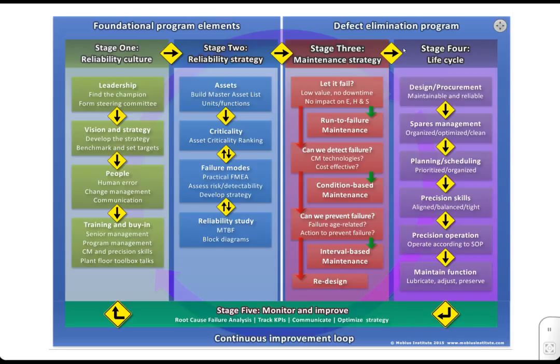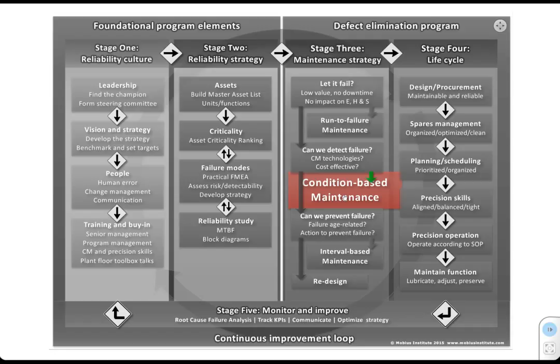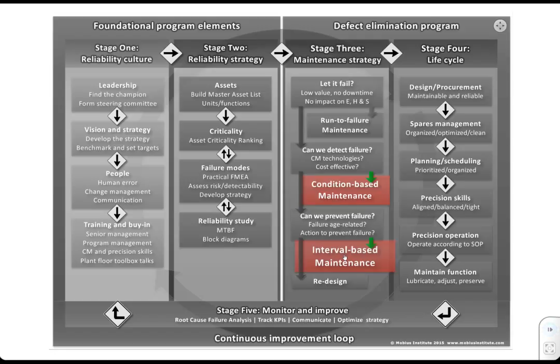Condition-based maintenance is actually different. Condition-based maintenance is the situation where we say, well, we are not going to perform maintenance unless the condition indicates that it's necessary. So no more time-based replacement of components when those components are actually perfectly fine. And that means that we will use our condition monitoring technologies, we'll plan our maintenance accordingly, but there'll still be some time-based and production cycle-based maintenance work, and we will identify equipment where we're not even going to take any special precautions, because everything we do has to have a basis in the economics of the situation.